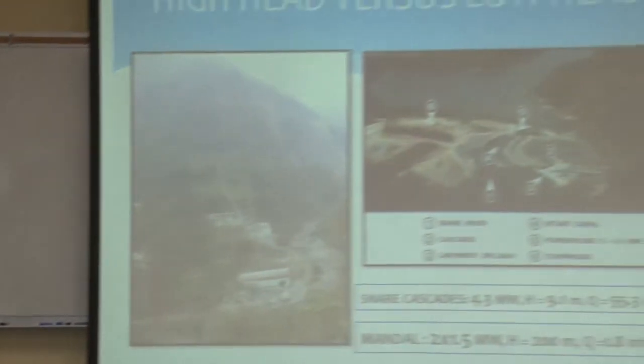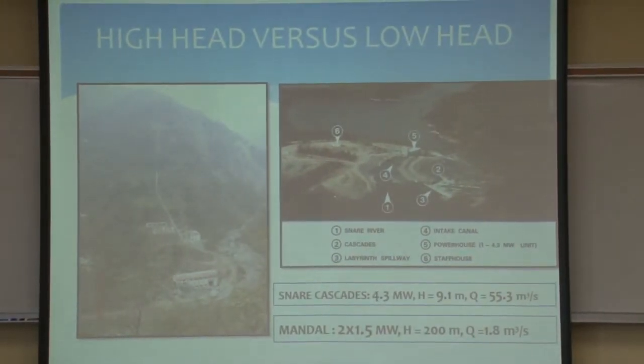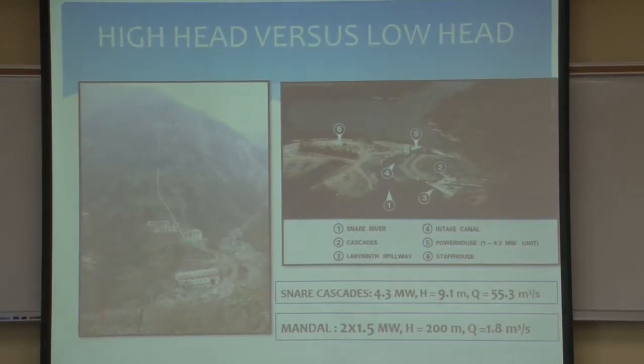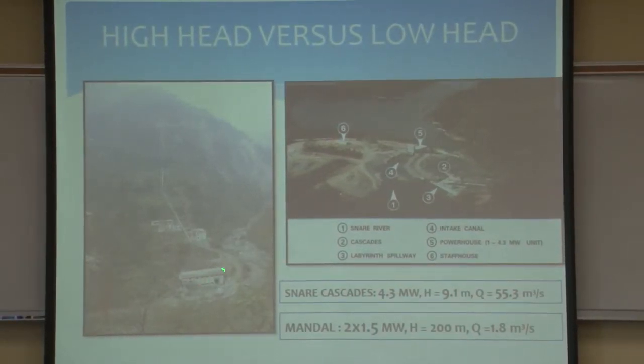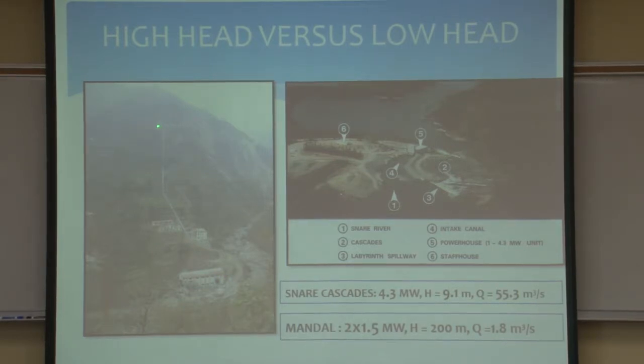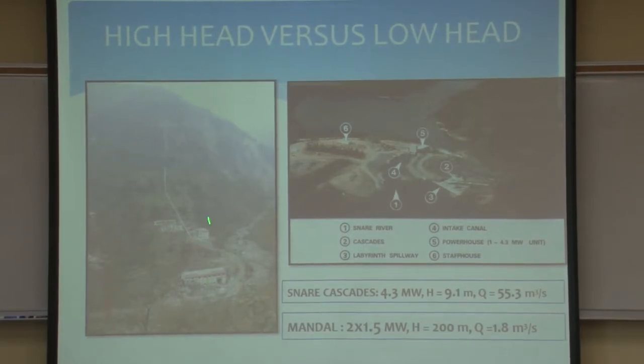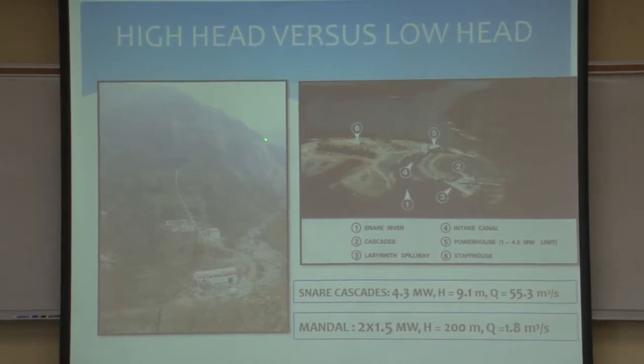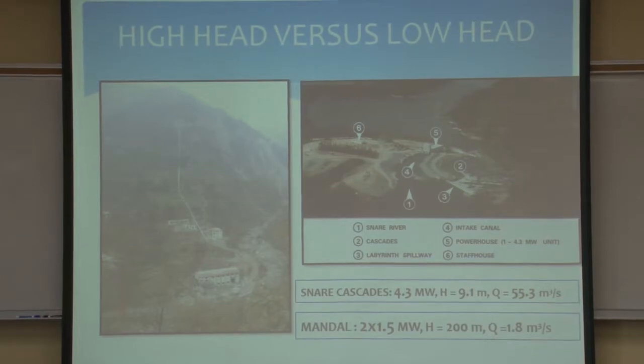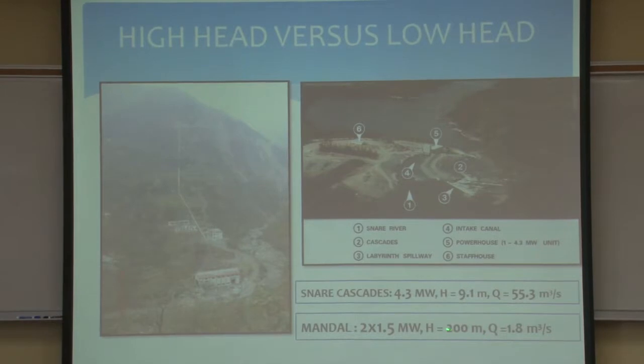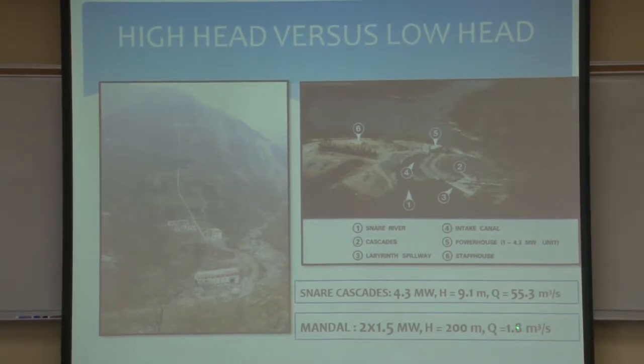I wanted to give you a contrast between a high head project and a low head project. This is a project in the Himalayan foothills in Punjab state. There's a couple hundred meters of fall between a canal that snakes along the side of the hill there and the power plant. It has a capacity of 3 megawatts, a drop in the order of 200 meters, and a design flow of about 1.8 cubic meters per second.